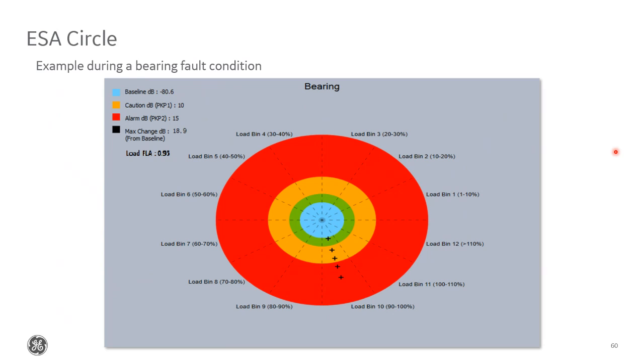Generally, for reciprocating loads, for example, in the motor setup settings, you would set, I think it's the load averaging filter that would take care of basically smoothing out that current waveform in the relay. It doesn't necessarily affect ESA per se. The only thing that ESA is really looking at is what load level you're currently operating in. I don't know if Paul or Mike, you have anything to add to that. I don't think it makes a huge difference. Right, I took it to mean, does it affect the ESA? But I think you're right, they are two different things. Don't really affect each other.